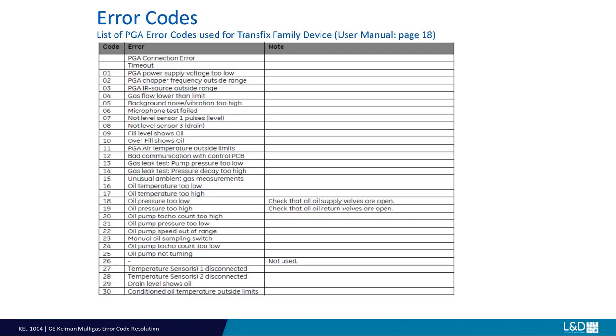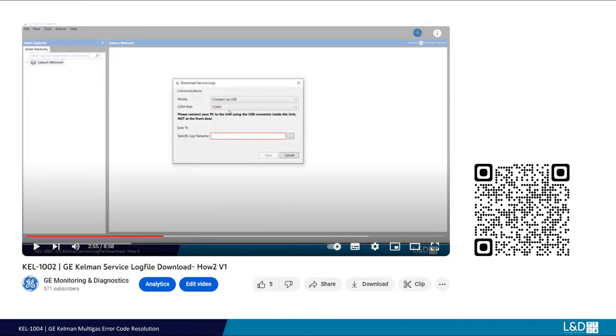If any error codes remain or reappear after an additional measurement, or these suggested procedures have been completed, please download the relevant service logs and send them to GE for analysis. These measurement system errors can be cross-referenced in the relevant equipment support manuals.